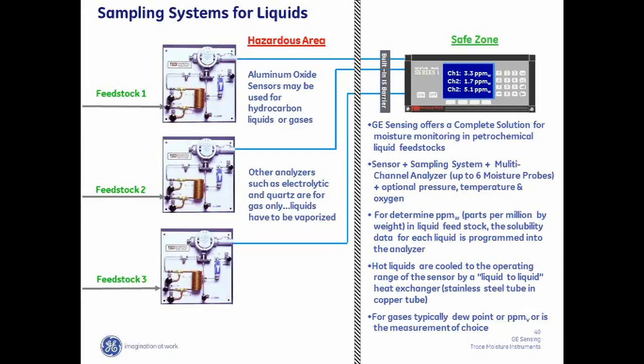In other words, the liquids are hot, so we have to cool the liquid down to the operating temperature of the sensor. The sensor is housed in an explosion-proof enclosure and then connected into the analyzer in the safe zone. So in this application, we're directly measuring the moisture concentration in liquid feedstocks. And very often our analyzers are looking at multiple channels. Our standard analyzer can look at 6 channels simultaneously.